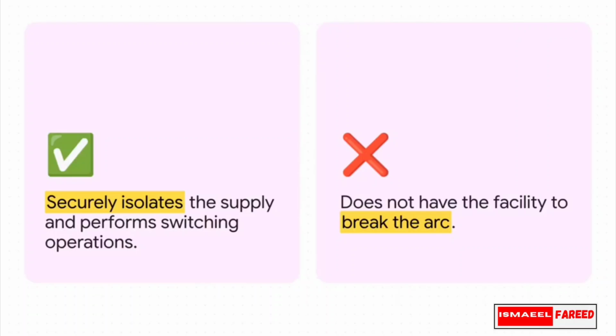So the crucial point is this. On one hand, an isolator securely isolates the power supply to perform basic switching, literally just turning a circuit on and off. But it has one critical limitation. It does not have the facility to break an electric arc. When a real circuit breaker trips during a fault, it safely snuffs out the literal arc of electricity trying to jump the gap. The isolator absolutely cannot do that. That's exactly why it can never be used as an active protective safeguard. It is purely for isolation, not active fault protection.